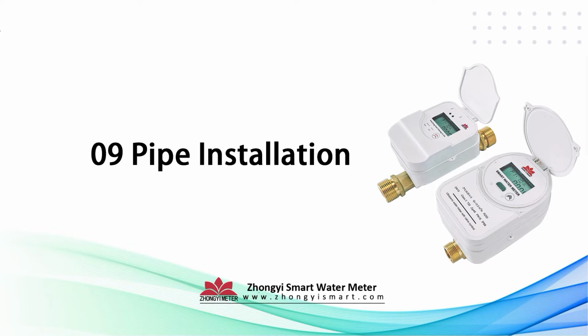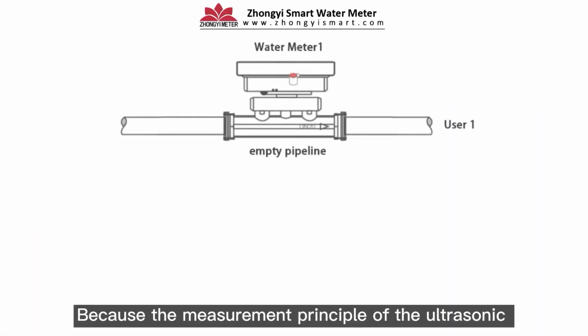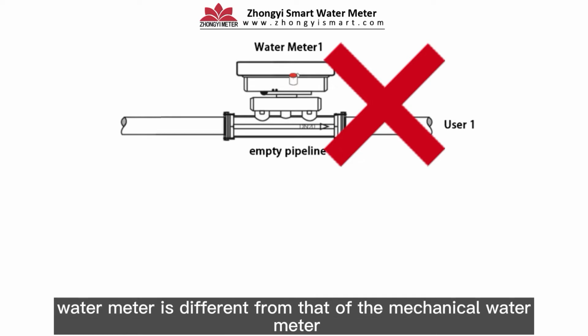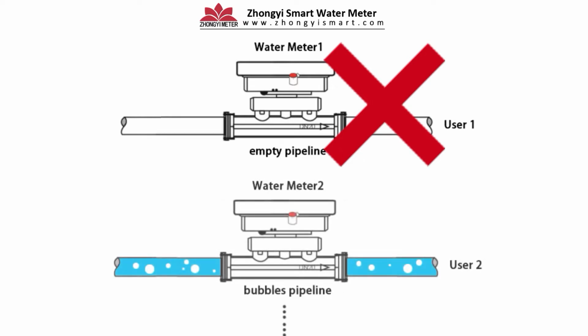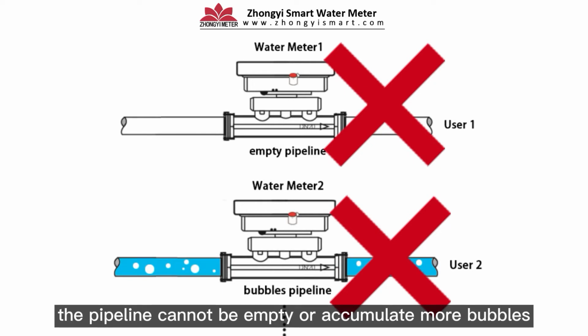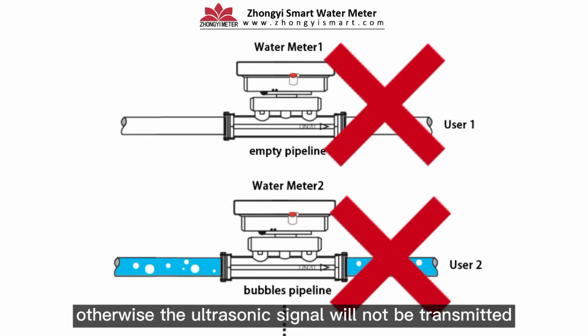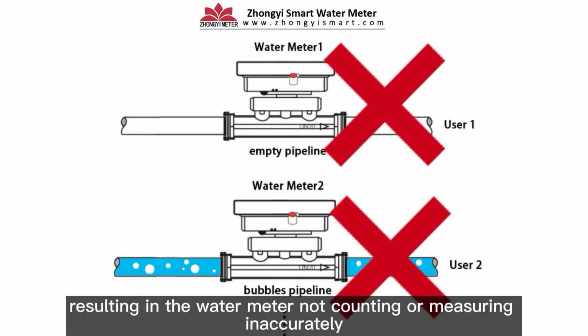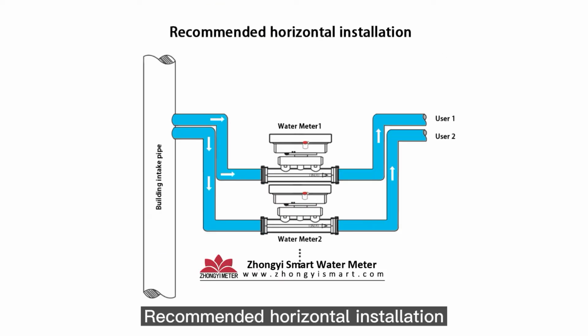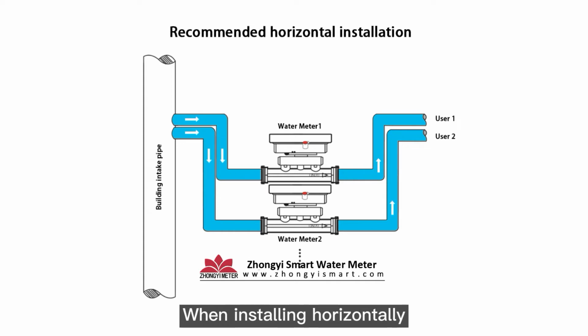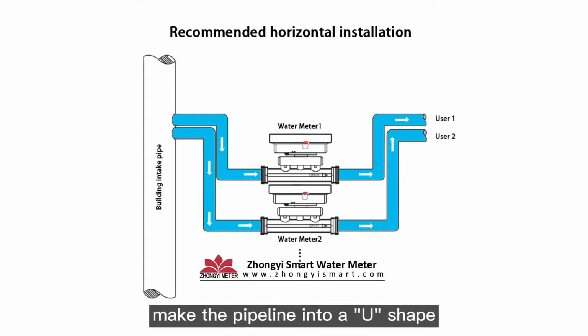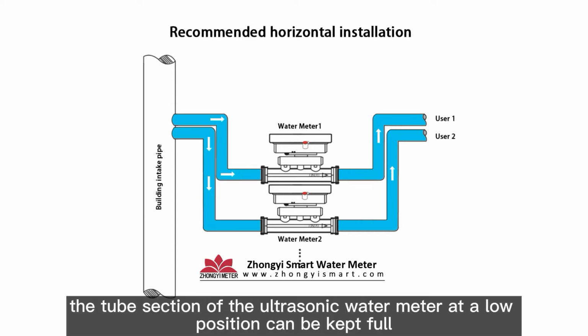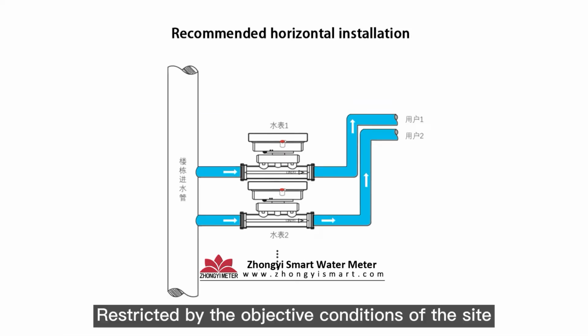Ultrasonic water meter water pipe installation. Because the measurement principle of the ultrasonic water meter is different from that of the mechanical water meter, the pipeline cannot be empty or accumulate many bubbles. Otherwise, the ultrasonic signal will not be transmitted, resulting in the water meter not counting or measuring inaccurately. Horizontal installation is recommended. When installing horizontally, make the pipeline into a U shape. In this case, the tube section of the ultrasonic water meter at a low position can be kept full, restricted by the objective conditions of the site.